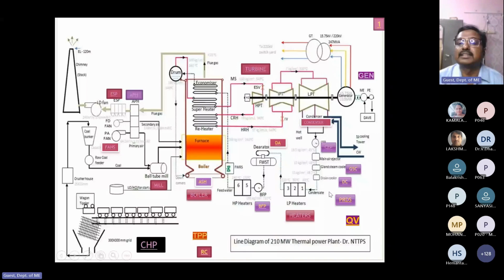If you observe here, there is a main air ejector after the CEP. The purpose of the main air ejector is to remove the non-condensable gases from the condenser. Here, we remove the gases because in the water some gases are mixed. So these gases are removed in the deaerator with the help of two concepts.